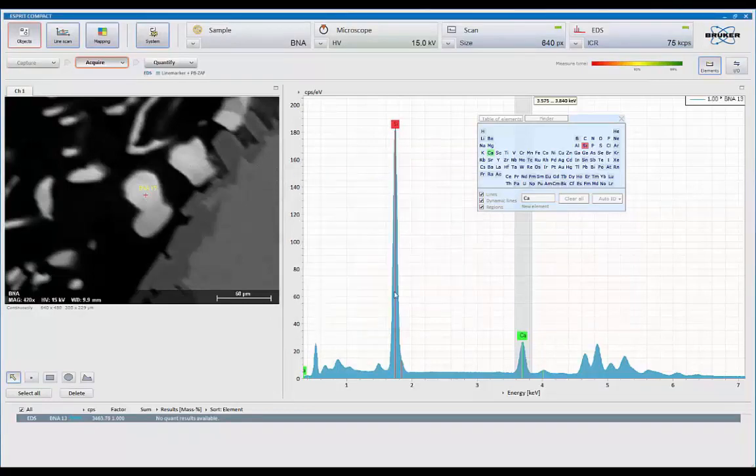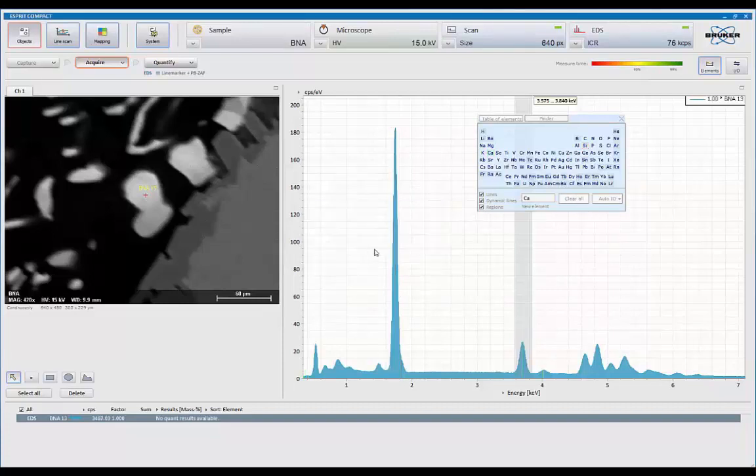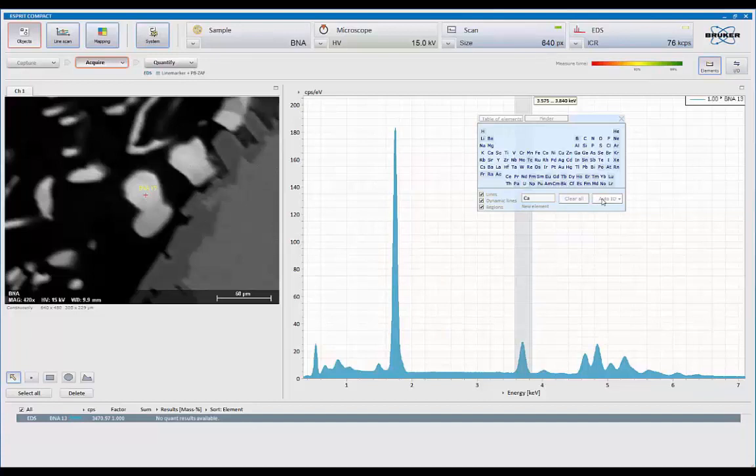In Auto ID, I can set elements I know I'm never going to bother with, so to speed up the analysis. And I also can set minimum detection limits. So in other words, I'm telling it, you do the majors, I'll do the minors. So with that, we clear out our identification and let Auto ID have a crack at this.